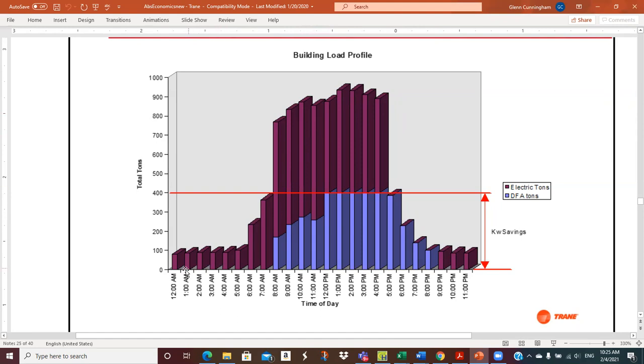And so you see in these off-peak hours, we're going to run the centrifugal because it's cheaper. So centrifugal, centrifugal, centrifugal, and all of a sudden, in this hour at 8 a.m., we jump up and we've got an 800-ton load. So guess what? We can't do all that with a 600-ton electric, so we've got to run both of them. So then the absorber gets fired up, and it's brought up. But see, it's kind of minimal. We're loading this centrifugal to its 600 tons max because it's still cheaper until we get to the on-peak.